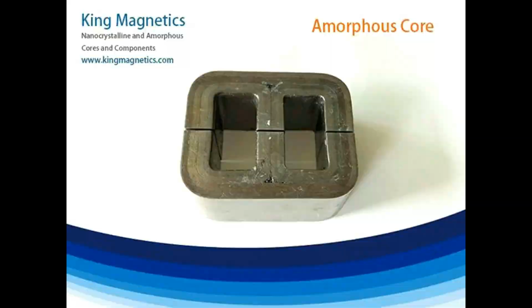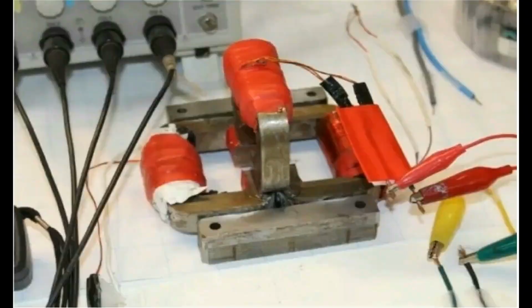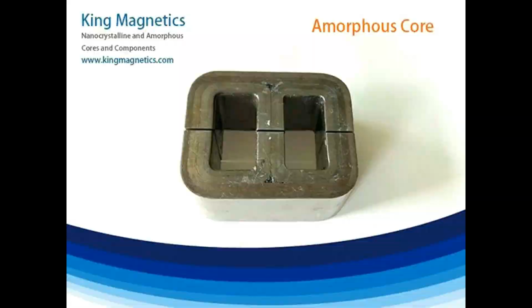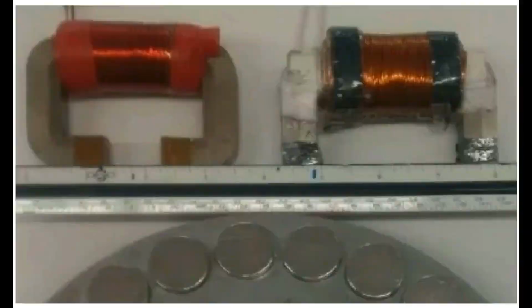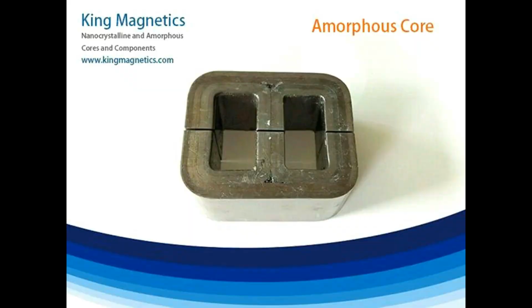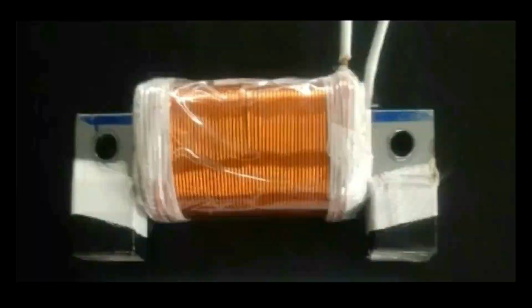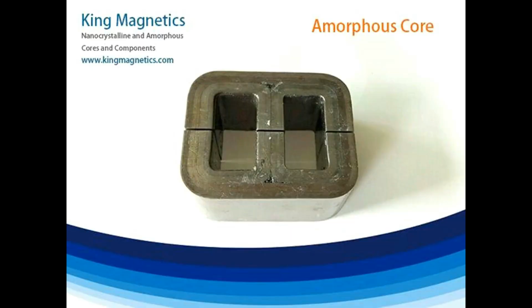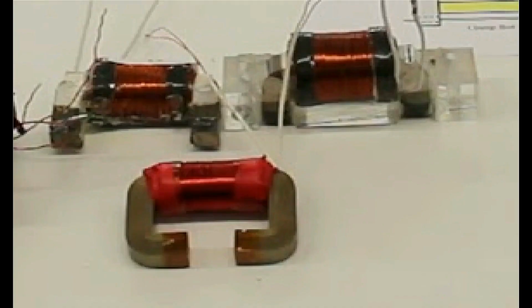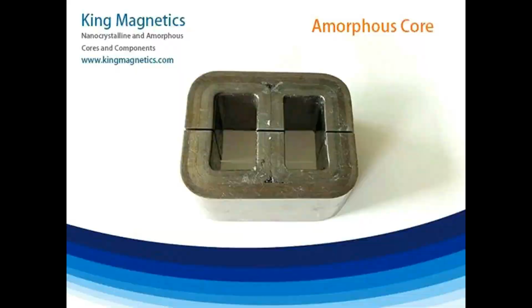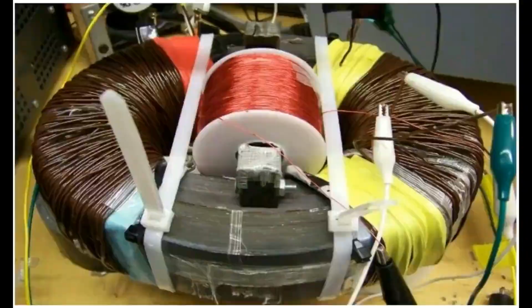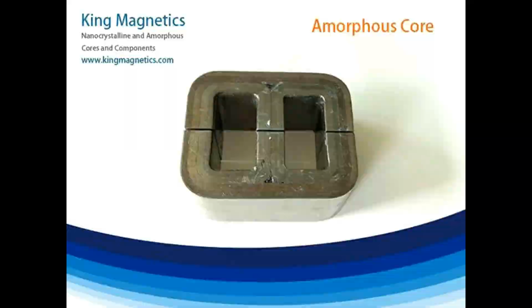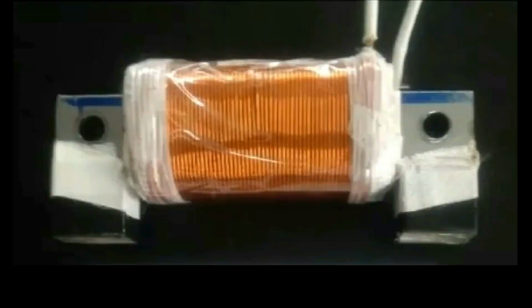On the downside, amorphous alloys have a lower saturation induction and often a higher magnetostriction compared to conventional crystalline iron silicon electrical steel. The main application of AMTs are the grid distribution transformers rated at about 50 to 1,000 kV amperes. These transformers typically run 24 hours a day and at a low load factor, average load divided by nominal load. The no-load loss of these transformers makes up a significant part of the loss of the whole distribution net. Amorphous iron is also used in specialized electric motors that operate at high frequencies of perhaps 350 Hz or more.